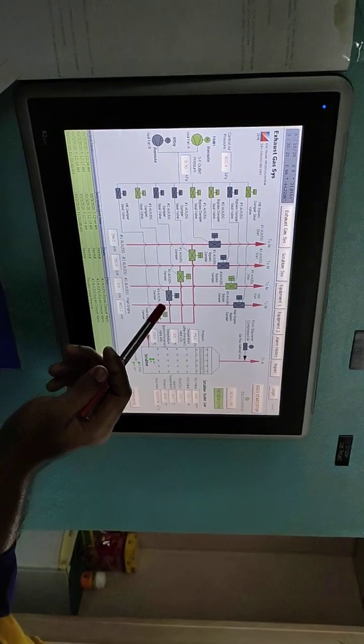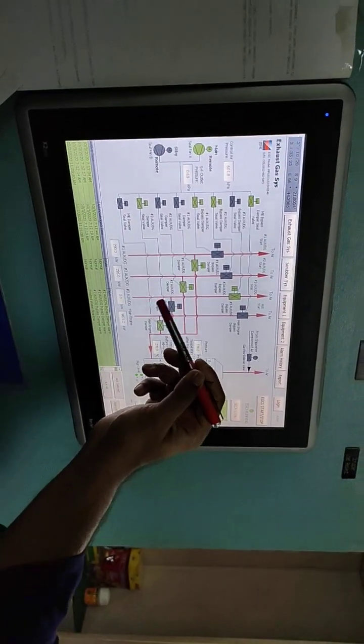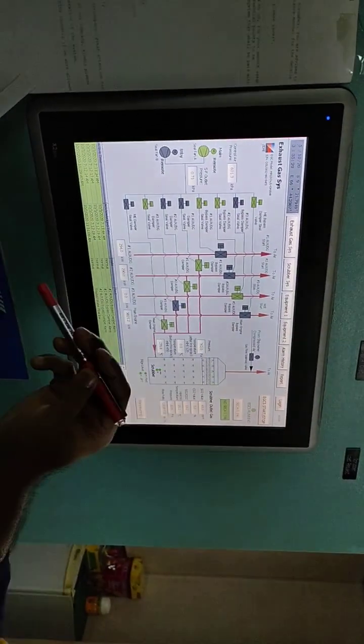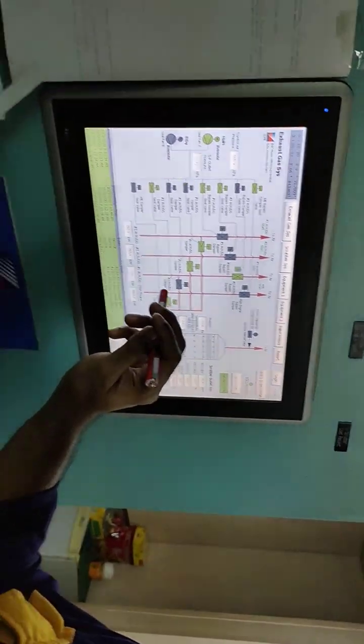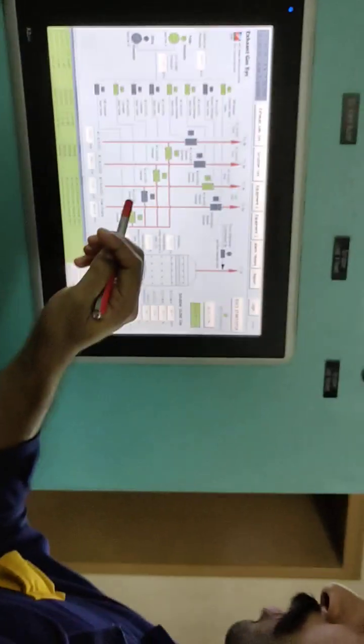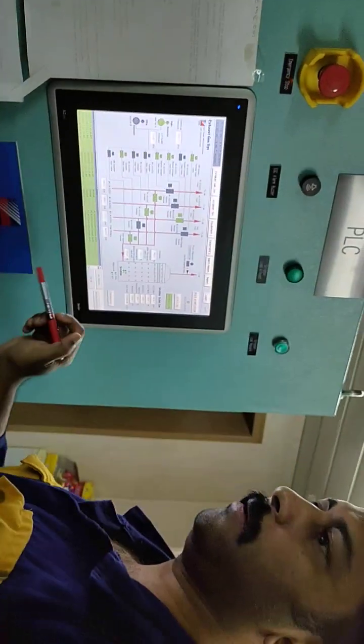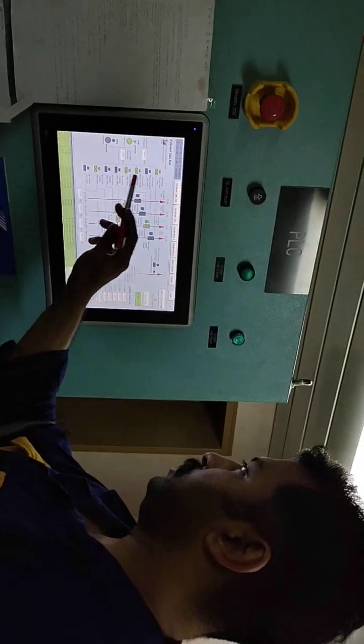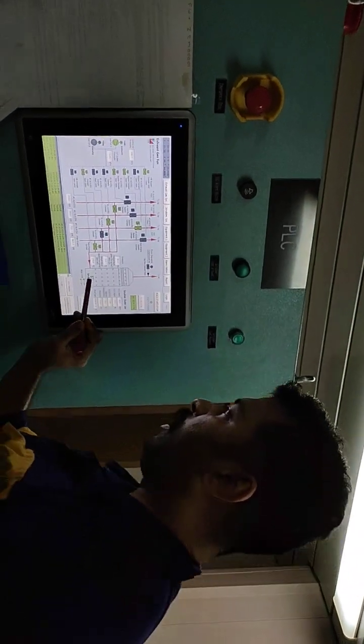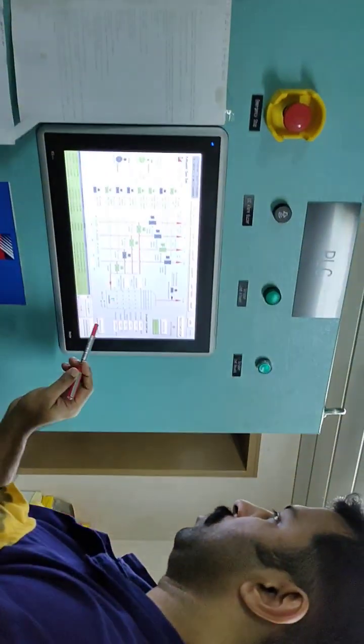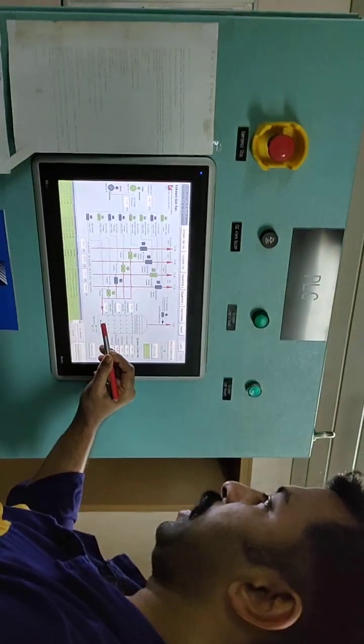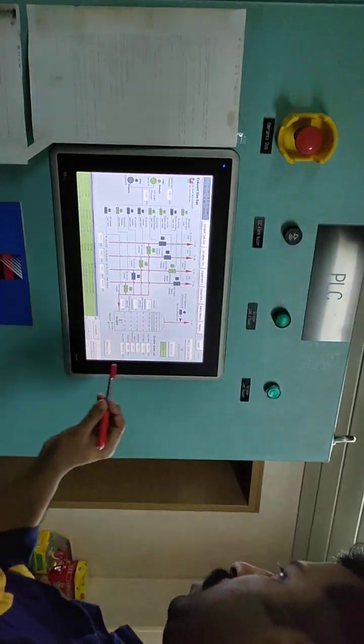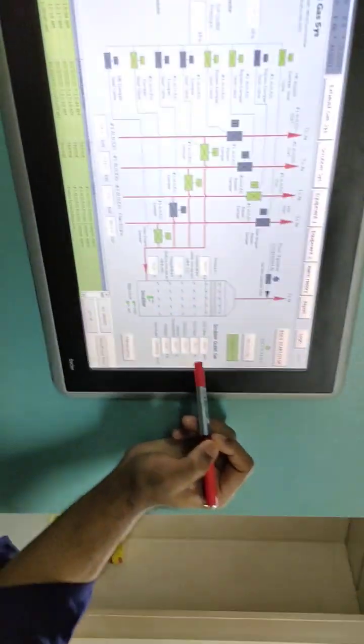If this valve is not closing or if this seal air is not going sufficiently, this gas may leak back to number 3 generator as back pressure, and it may cause trouble in starting this generator. In starting, you may have a problem because all the exhaust line as well as the valve will be filled with the other exhaust. It may give you trouble in starting the generator. Okay, the bypass seal valves are finished, and you have two safeties, high level and high-high trip. High level alarm will come; at high-high the system will stop, because if the water is not draining continuously overboard, the water will start filling up in the tower, and once it reaches high level, an alarm will come, and at high-high the system will completely stop.